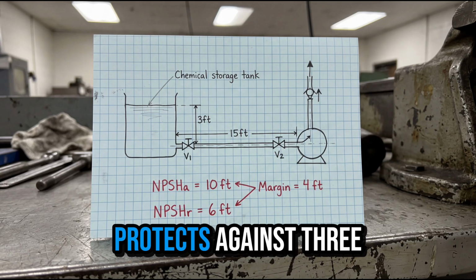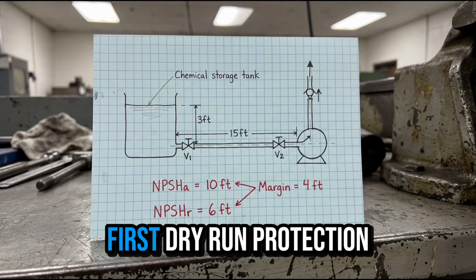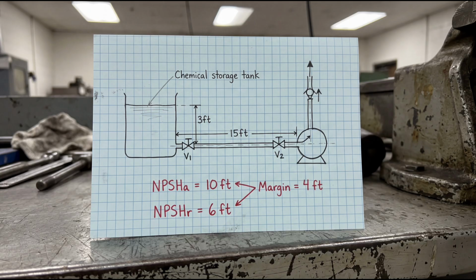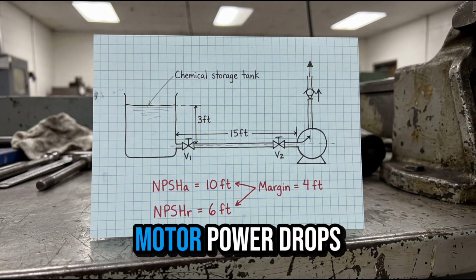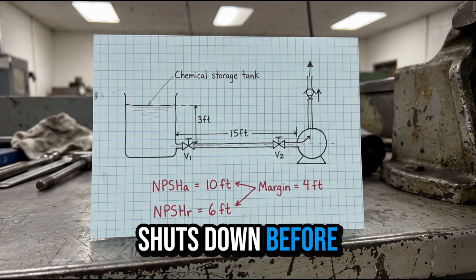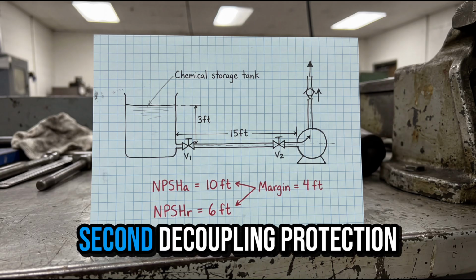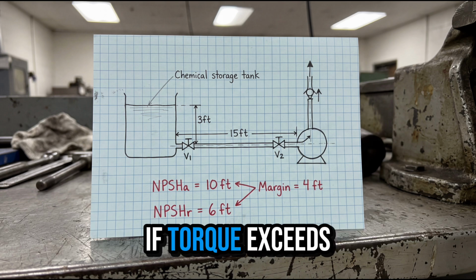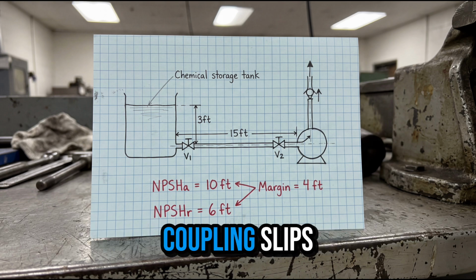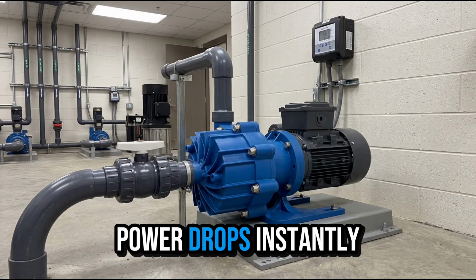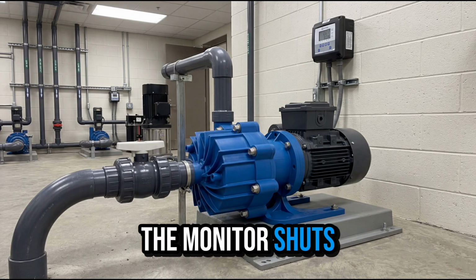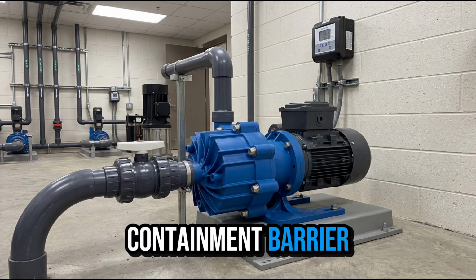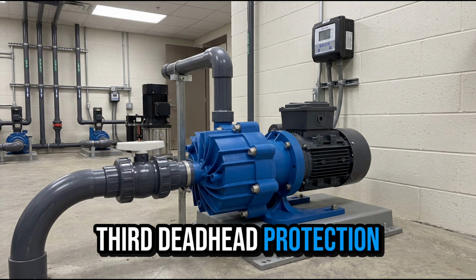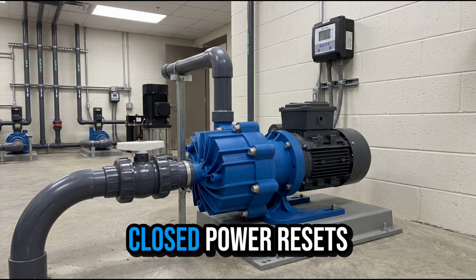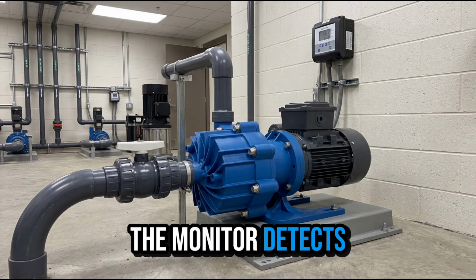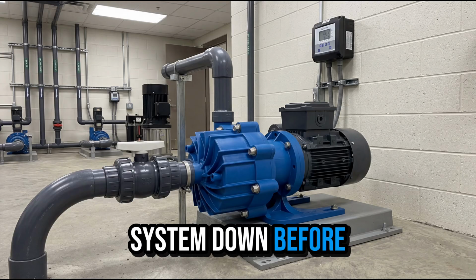The power monitor protects against 3 failure modes. First, dry run protection. When liquid is lost, motor power drops and the system shuts down before damage occurs. Second, decoupling protection. If torque exceeds limits, the magnetic coupling slips. Power drops instantly. The monitor shuts down the motor and protects the containment barrier. Third, deadhead protection. If discharge is closed, power drops, the monitor detects this and shuts the system down before internal damage occurs.